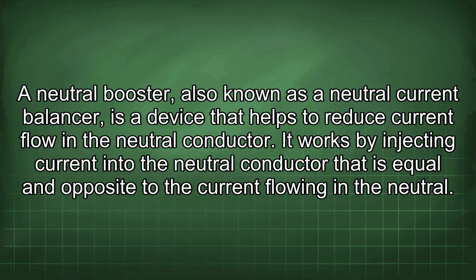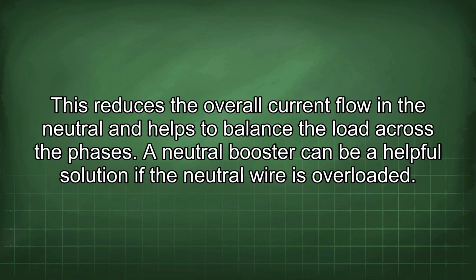A neutral booster, also known as a neutral current balancer, is a device that helps to reduce current flow in the neutral conductor. It works by injecting current into the neutral conductor that is equal and opposite to the current flowing in the neutral. This reduces the overall current flow in the neutral and helps to balance the load across the phases. A neutral booster can be a helpful solution if the neutral wire is overloaded.